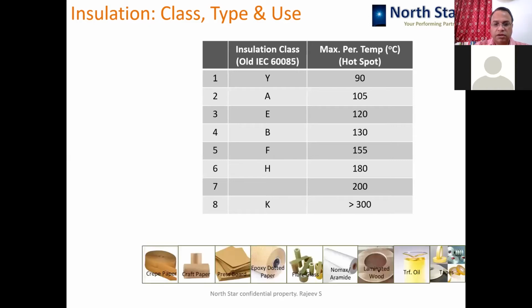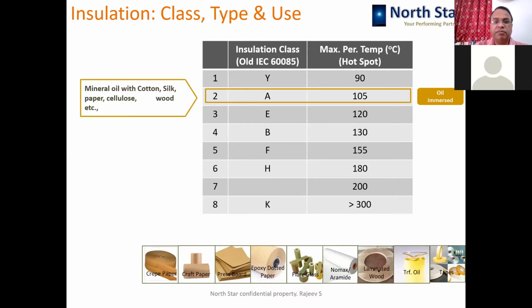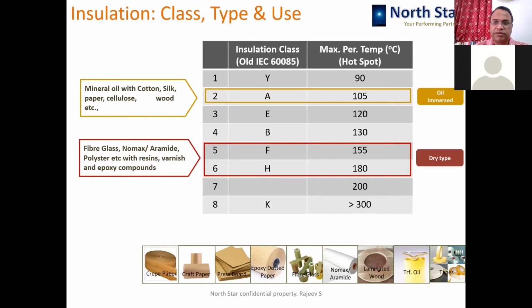If you look, these are the different solid insulation materials. Class A, 105 degrees centigrade, is our standard oil immersed transformers, which are made from cellulose-based insulation along with the petroleum-based or mineral-based insulating liquid, that is mineral oil or transformer oil. The second category is dry type transformers, which apply 155 and 180 degrees centigrade classes of insulation. Typically, VPI transformers are 155 degrees, and CRT transformers can have 155 as well as 180 degrees centigrade classes. So these are dry type transformers.